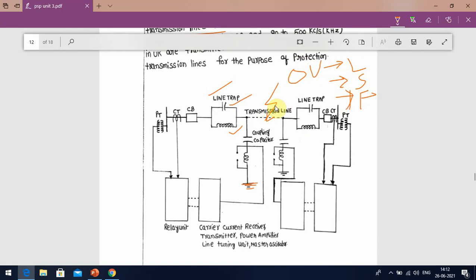Therefore, the production of over voltages puts stress on the coupling equipment and the line trap unit. So a non-linear resistor in series with a protective gap is connected across the line trap and the inductor of the coupling unit, in order to overcome those over voltages.